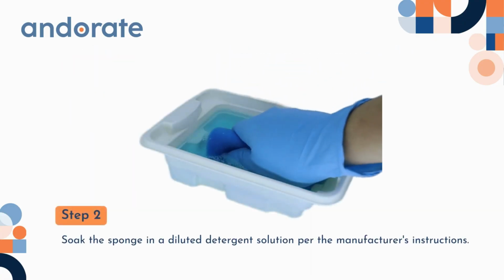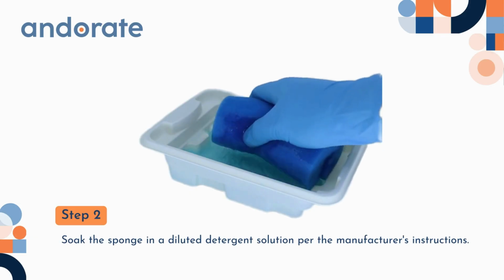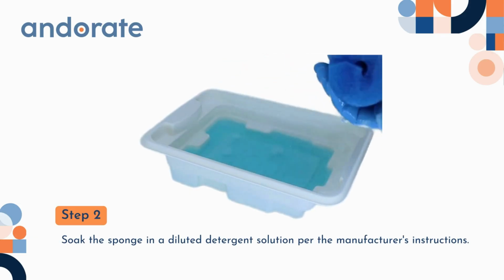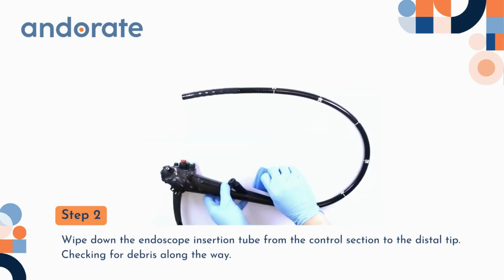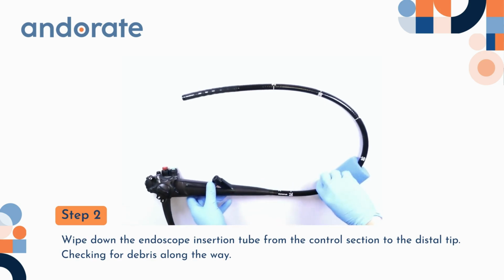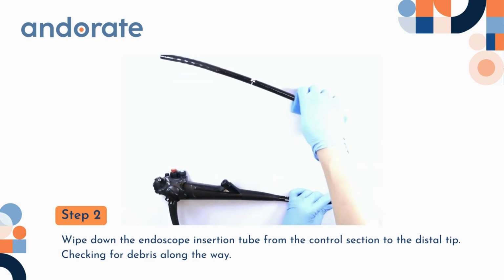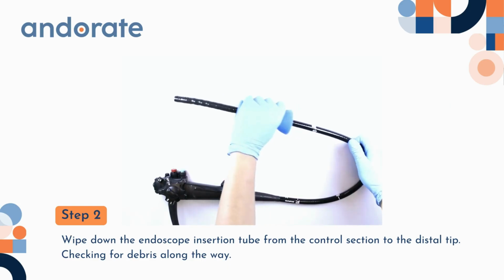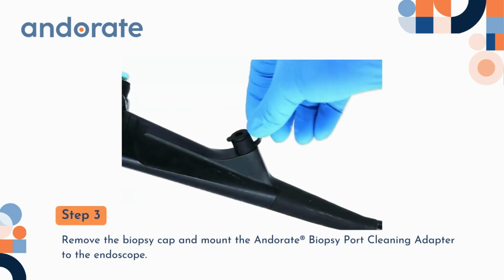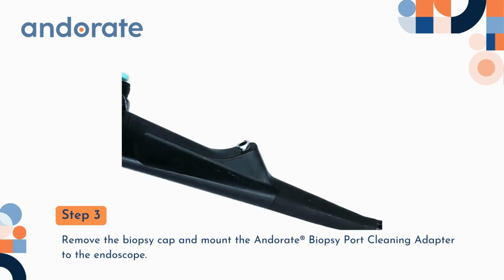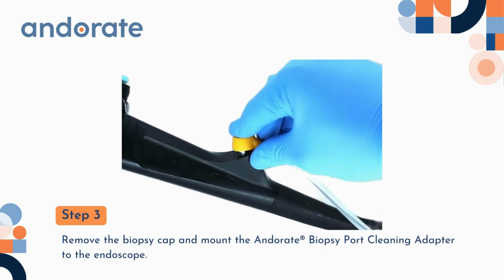Step 2. Soak the sponge in diluted detergent solution per the manufacturer's instructions. Wipe down the endoscope insertion tube from the control section to the distal tip, checking for debris along the way. Step 3. Remove the biopsy cap and mount the Andorate biopsy port cleaning adapter to the endoscope.